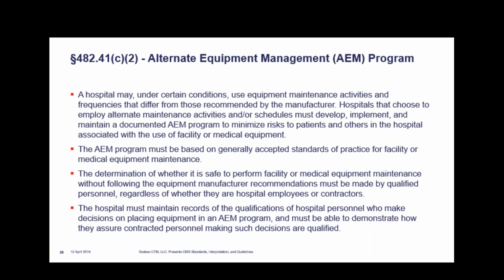So again, generally accepted practices determine whether it's safe to perform facility and medical equipment maintenance without following the equipment manufacturer's guidance. Hospitals must maintain records of qualifications of hospital personnel who make the decision to place the device on AEM. So for all of you that have an AEM, keep your qualifications ready and posted. Very similar qualifications as far as working on a medical device. You've got to be competent in order to make that assessment.